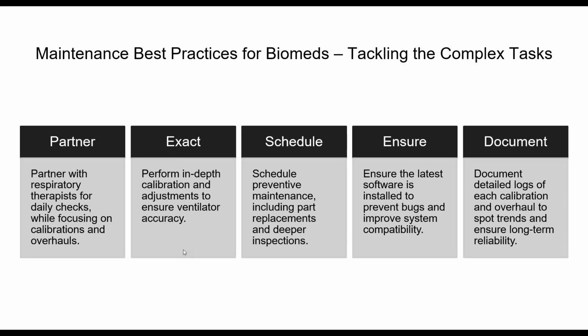You should focus on your calibrations and your overhauls. Be exact - this is one area where I'll mention a couple of additional levels that I like to do when I work on ventilators. Perform the in-depth calibration and adjustments. There are certain ventilators that over time I've become familiar with enough that it's a nominal amount of additional time for me to go through the calibrations twice to improve the accuracy and precision of the performance of all aspects.